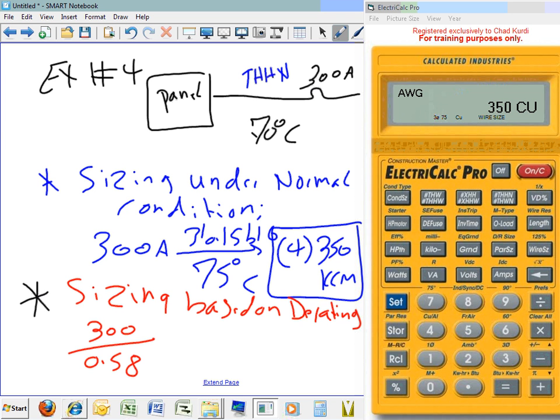But that's not what we normally do as designers. We start with a load, we find a conductor. We rarely would ever be asked, here's a 4/0, can you find how many amps you can pull out of this? It's sitting right there and we need to tie something to it. Could happen, but rarely. Usually, I need a 200 amp panel, find me a conductor for it, right? Okay, so I need a friend to give me the answer. 517 amps. And feel free to approximate 0.5 up, less than 0.5 down, right? 517. Okay.